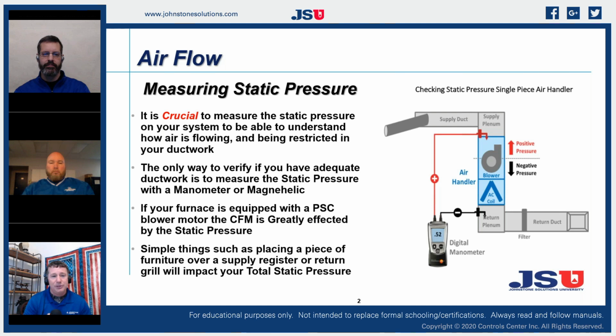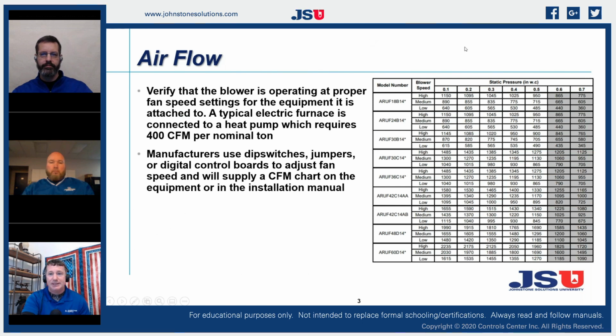So if we have a 1-inch filter in that air handler and it did not come with the filter from the factory, we're not reading proper static across that thing. So be aware of proper static pressure readings because it throws those motors off drastically.